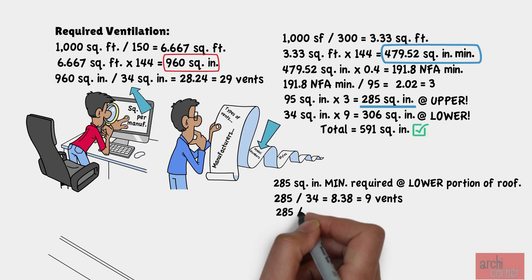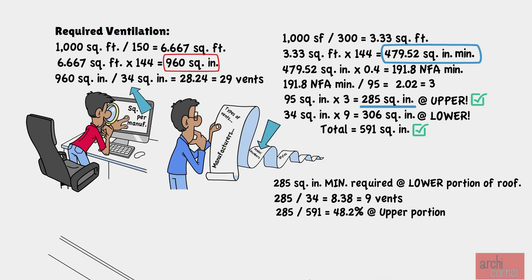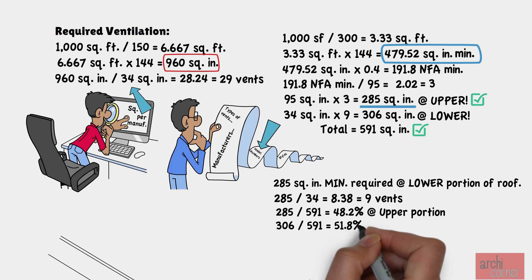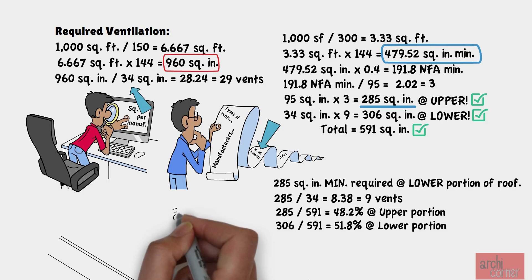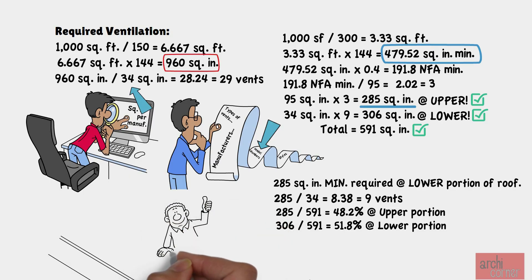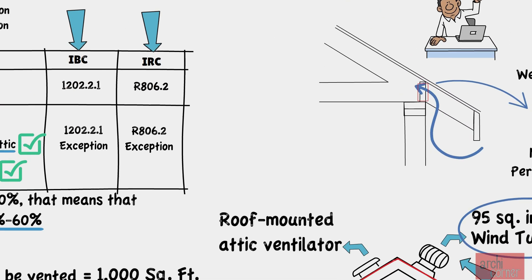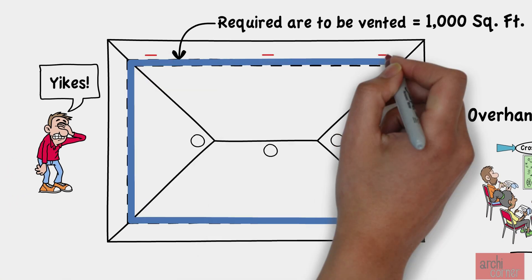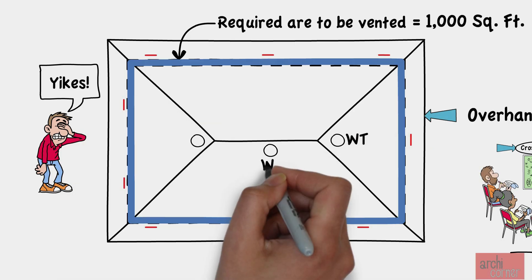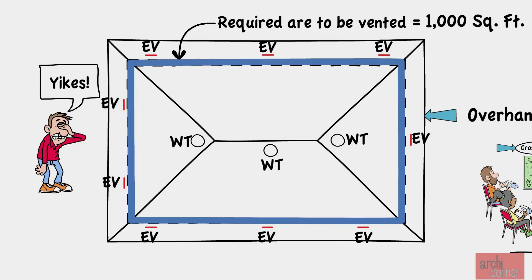This meets the minimum requirements. We confirmed that 48.2% of venting is provided on the upper portion with wind turbines and 51.8% in the lower portion with eave vents, keeping the upper venting between 40% and 60% as required. On the roof plan, we place three wind turbines on top and nine under-eave vents around the building, spreading them out to allow for cross ventilation.